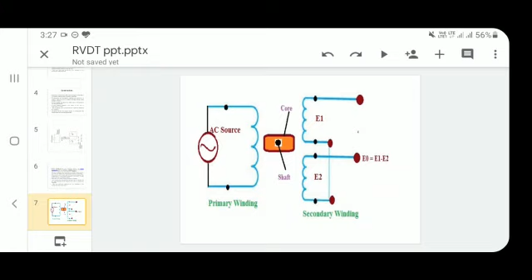The typical RVDTs are linear, available from plus 40 to minus 40 degrees. Sensitivity is about 2 millivolt to 3 millivolt per degree of rotation, and the input voltage is 3 volt RMS at a frequency ranging from 400 Hz to 20 kHz. Based on the movement of the shaft in the transformer, three conditions will be produced: when the core is at null position, when the core rotates in clockwise direction, and when the core rotates in anti-clockwise direction. We will learn here one by one.